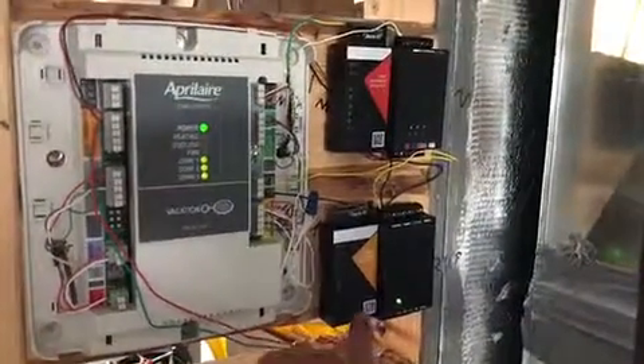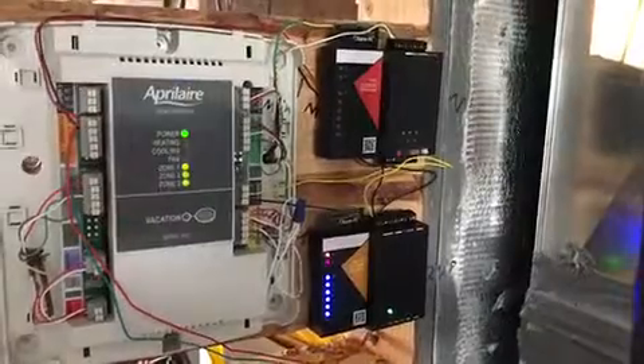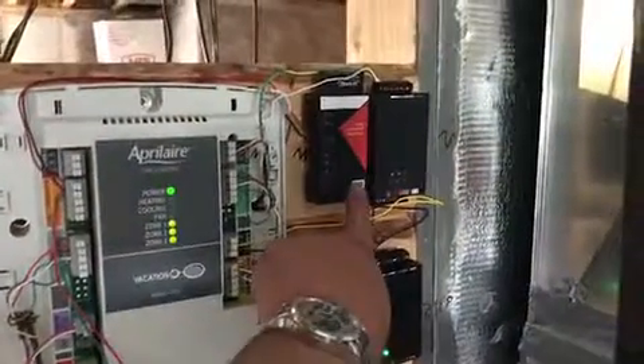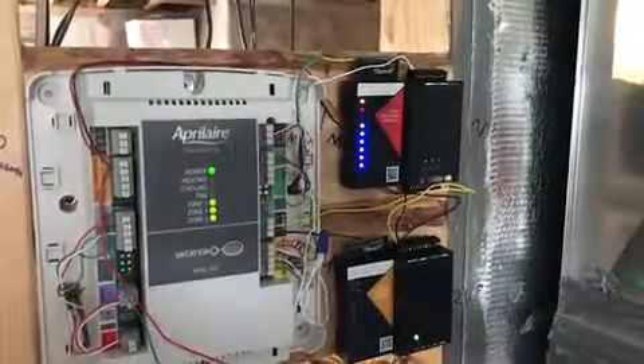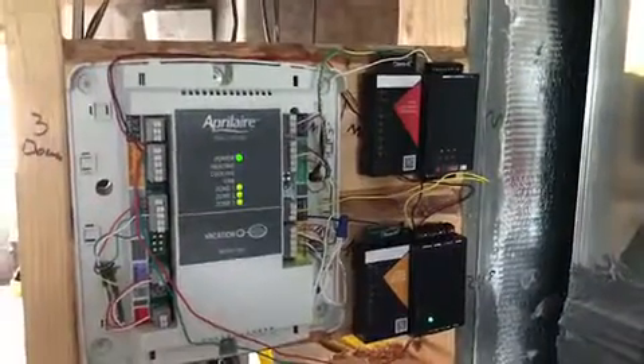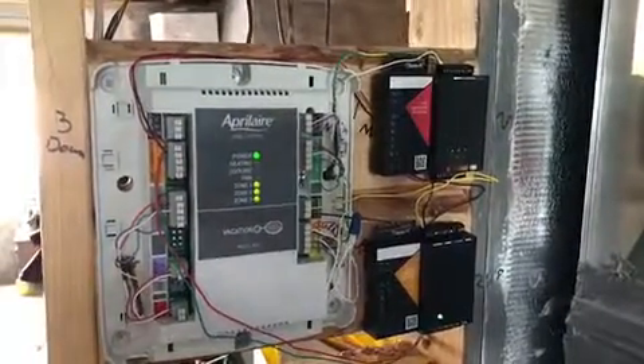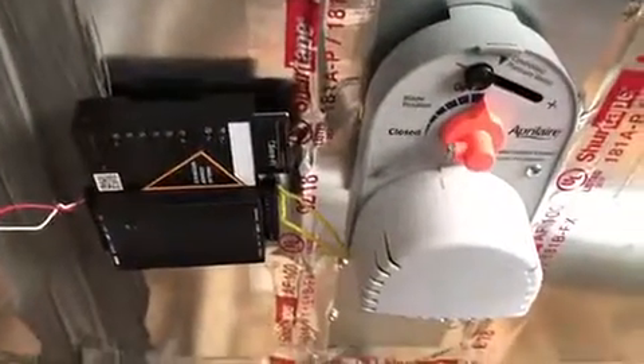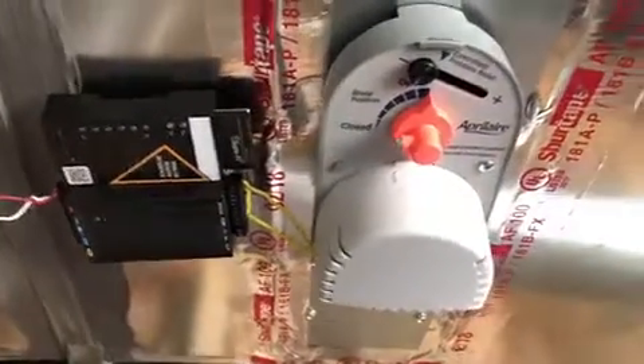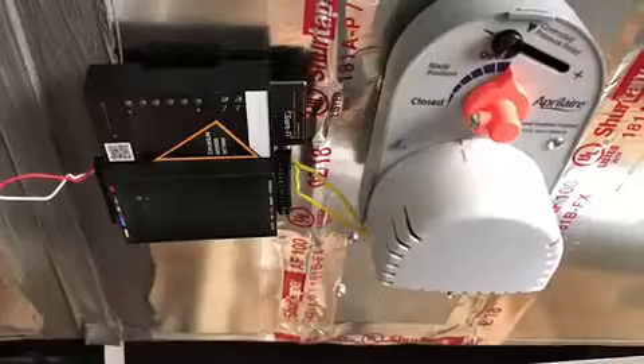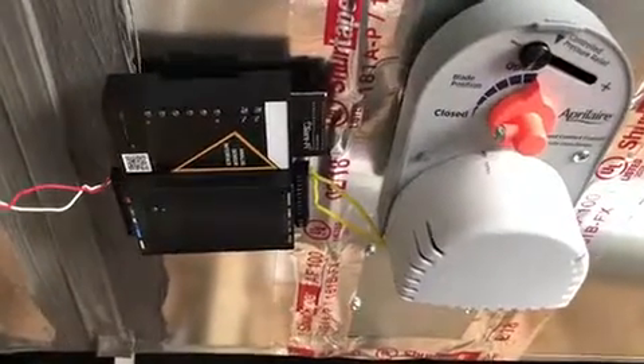While I'm here, let me just show you the testing. Okay, that's out to the damper, and this is up 2 flights to the upstairs where the new thermostat is. So here we have the analog bridge connected to the zoning controller here in this duct. You can see right now it's open. We're going to go ahead and get that shut down so you can see what happens.